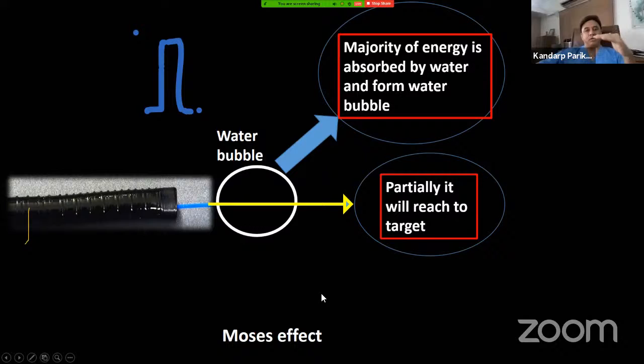So mainly the fragmentation or dusting of the stone occurs because of the absorption of this heat on the surface of the stone. That is a photothermal effect, and that will produce small crevices in the stone, as well as there are some water droplets within the crevices. They will absorb the energy and they again expand, and then they burst. When they burst, they produce further fragmentation or dusting. So that's how mainly it is a photothermal effect which is responsible for the fragmentation or dusting. Second is a photoacoustic effect, which has a very small contribution for the lithotripsy. And then finally, it is a photochemical, which is very, very minimum. This effect is known as a Moses effect, which was described in year 1984.